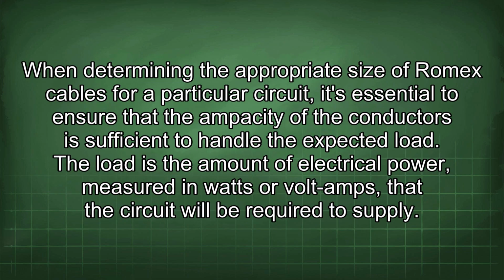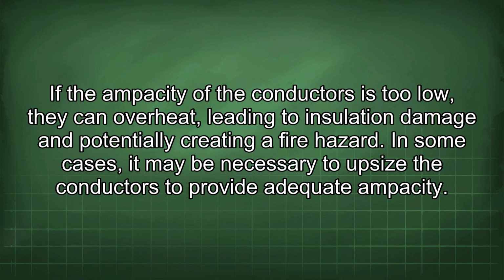When determining the appropriate size of Romex cables for a particular circuit, it's essential to ensure that the ampacity of the conductors is sufficient to handle the expected load. The load is the amount of electrical power, measured in watts or volt amps, that the circuit will be required to supply. If the ampacity of the conductors is too low, they can overheat, leading to insulation damage and potentially creating a fire hazard. In some cases, it may be necessary to upsize the conductors to provide adequate ampacity.